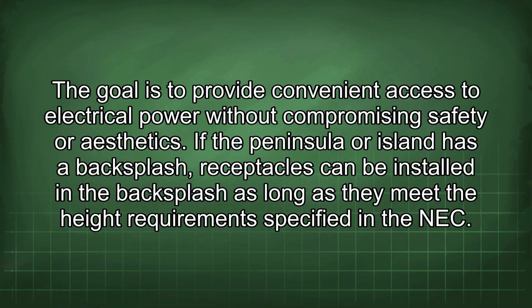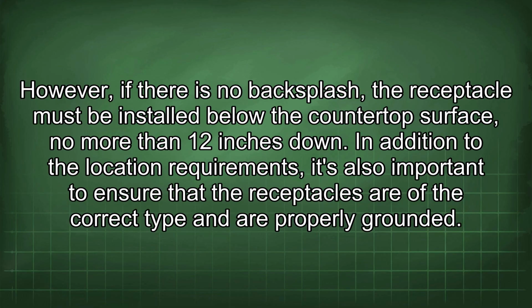If the peninsula or island has a backsplash, receptacles can be installed in a backsplash as long as they meet the height requirements specified in the NEC. However, if there is no backsplash, the receptacle must be installed below the countertop surface, no more than 12 inches down.